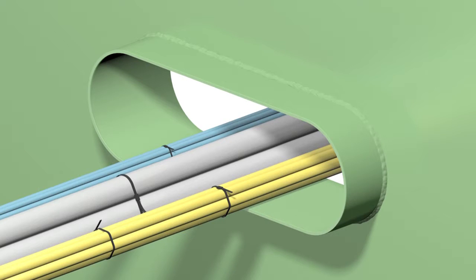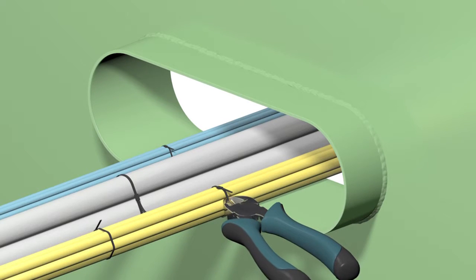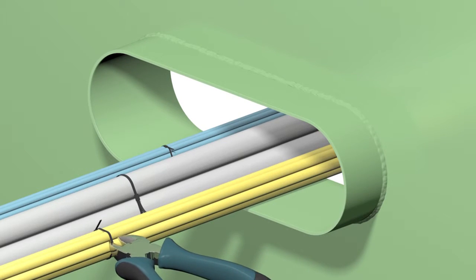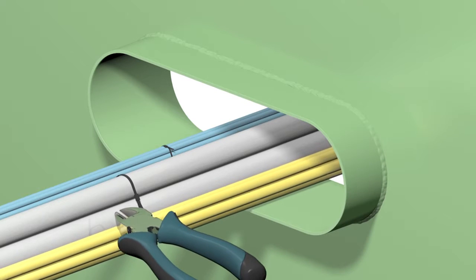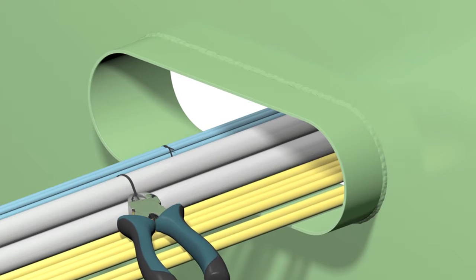Although the cables can be ducted in random order, a well-organized pulling of cables makes the installation a lot easier. The cables should not be pulled too tight and an overfill of cables should be avoided. There must be enough space to provide all cables with an insert sleeve. The cable tie wraps have to be removed to create enough play in between the cables to enable cleaning and insertion of the rise cable sleeves.